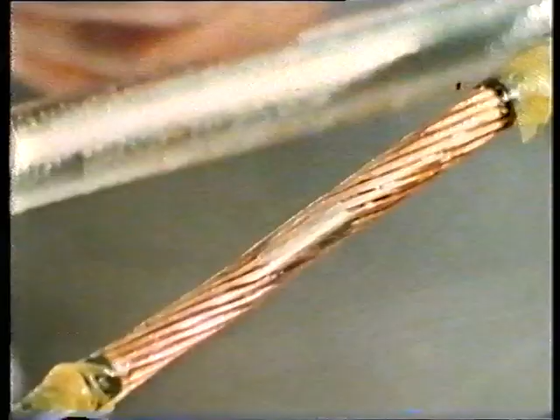Now, the impregnated paper is added. This is done in steps, each overlapping the previous one to avoid any weakness. The reinstatement of the insulation is completed by the application of metallized paper screening tape. As before, the jute filler is laid between the cable cores to give the correct shape and to fill the gaps.